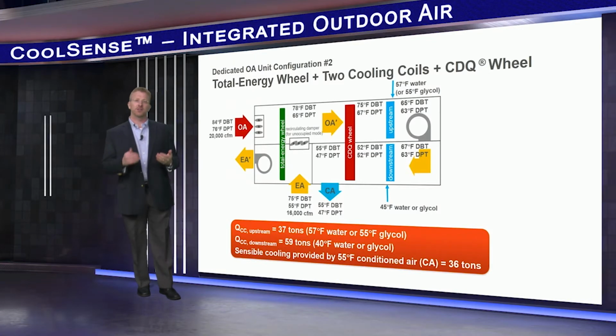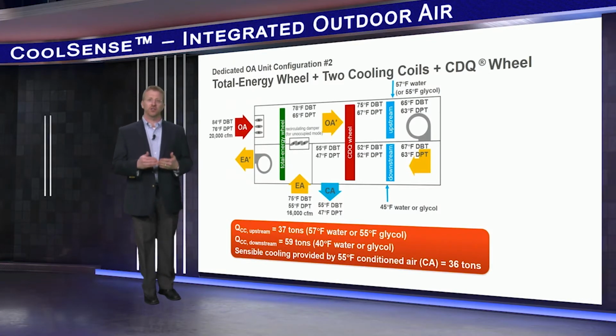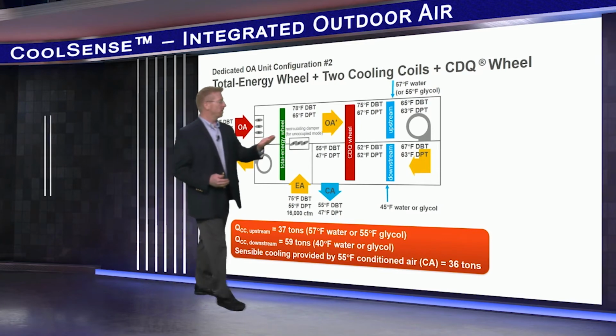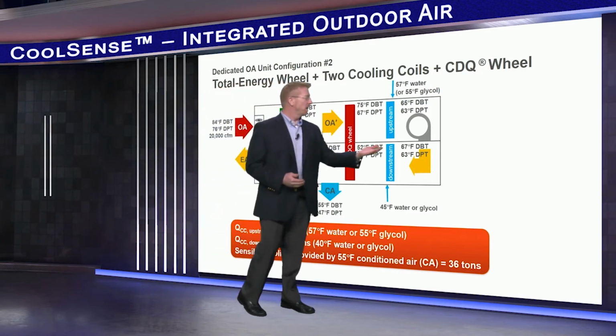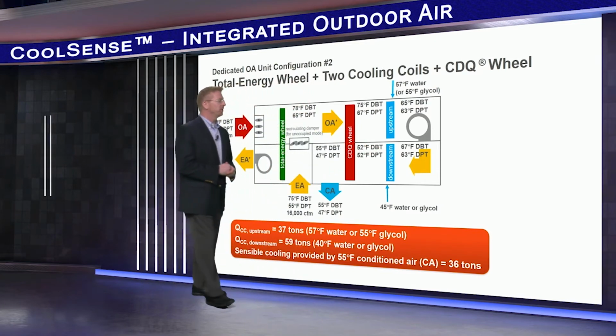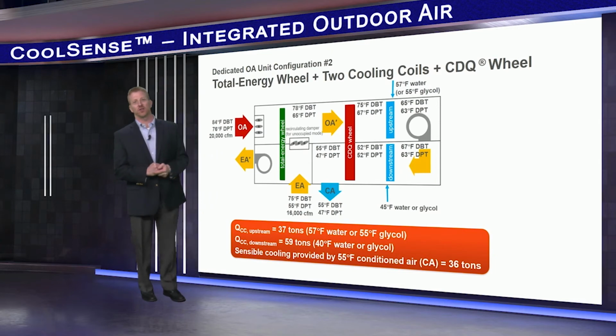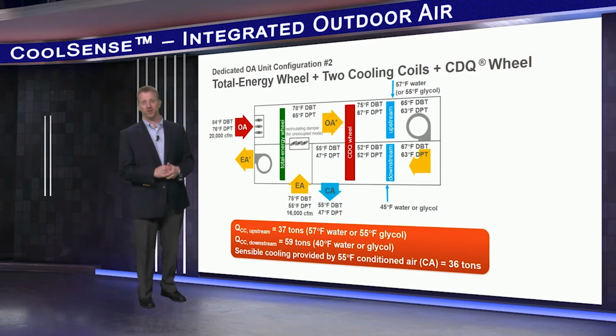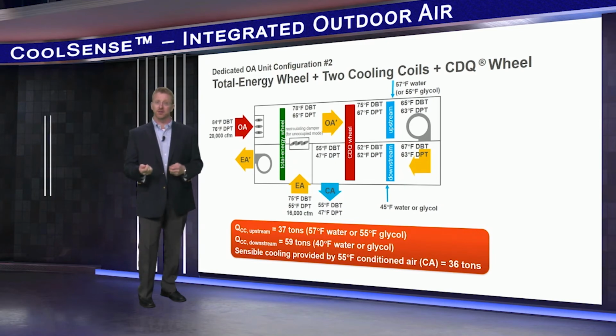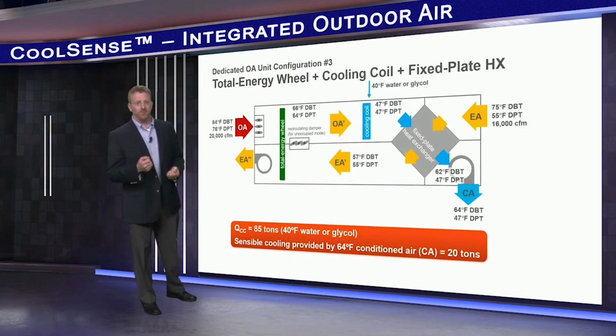Now once again, same DOAS unit, just adding the upstream warm water coil and splitting the load again. Here you see that this shifts 37 tons of load to the warm water chiller, further reducing the load on the cold water chiller from 96 tons to 59 tons. Now only one more configuration.